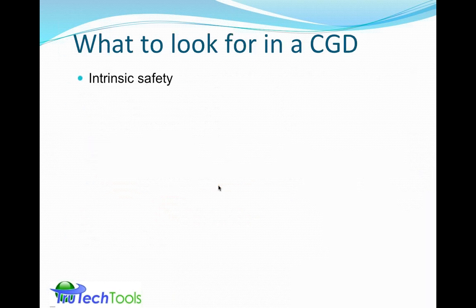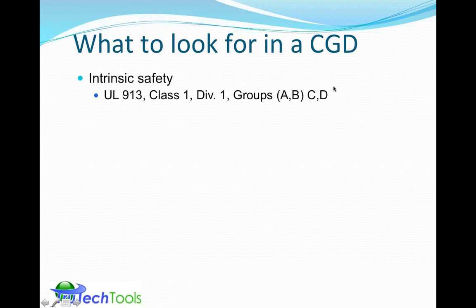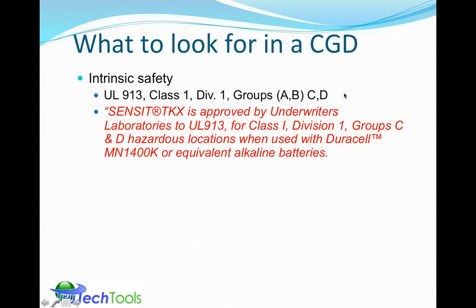So what do we end up looking for in a combustible gas detector? Intrinsic safety, and that would be noted or marked on the instrument with a marking such as UL 913, which is an intrinsic safety standard, and indicate Class 1, Division 1, in groups C and D for sure, must have that, or it could be A and B. And these talk about the different atmospheres that are present, but the C and D cover the market that we're looking at. You'd see a mark or written description such as this here, in the sense this is lifted directly from the Sensit TKX instruction manual, where they say it's approved for Underwriters Laboratory 913, Class 1, Div 1, Group C and D. So that complies with the intrinsic safety intent of the standard.